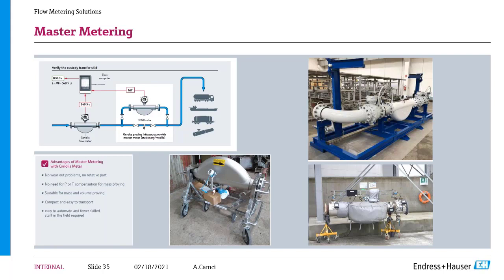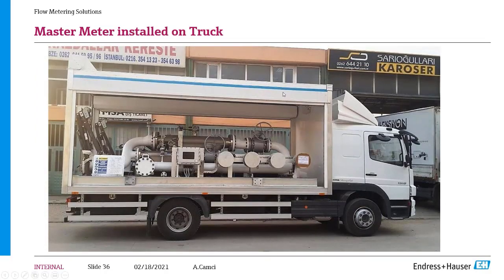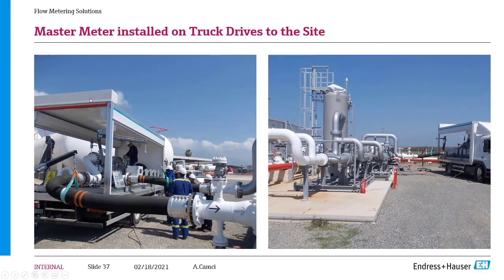The transport of this is maybe easy within a terminal, but if you have multiple terminals, what can Endress+Hauser offer to you? Here you see the master metering skid, with one 10-inch and one 6-inch flow meter. It is delivered skid mounted and also installed on a truck. It has all the necessary auxiliaries, like cranes to lift flexible piping to connect to the measurement skids. All cables are reeled on these bundles, and with all the wires it is ready for operation. What I mean by operation: the truck is on site, with the cranes provided the flexibles are connected to the measurement system, and all the cables are connected to the respective junction boxes, which communicate with the flow computing system in the safe area. You can then test the duty meters under real-life operational conditions.